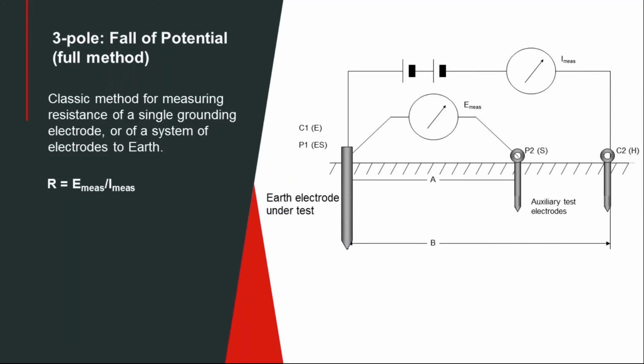Put it that way. Okay, so now we'll look at three-pole fall of potential. This is the most fundamental, most accurate, most reliable means of doing a ground test. In this case, you have a three-terminal tester. I could have mentioned also with respect to doing soil resistivity, ground testers come in 3-terminal and 4-terminal models. If you're going to do soil resistivity, you must have a 4-terminal model, and we saw why, because we showed you that little diagram which required 4 terminals. A 3-terminal tester can do resistance just fine, but it can't do resistivity, so keep that in mind.